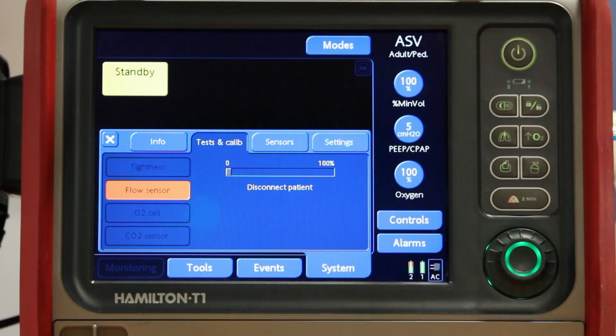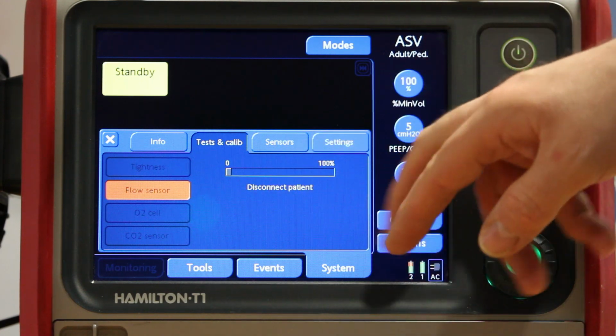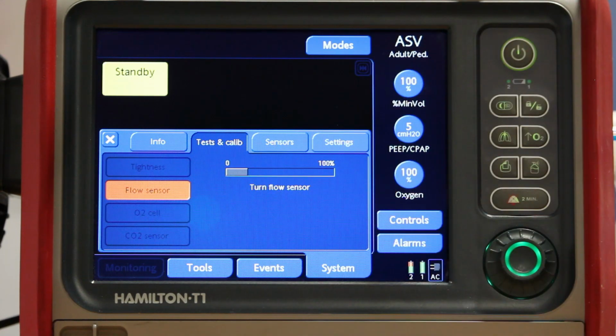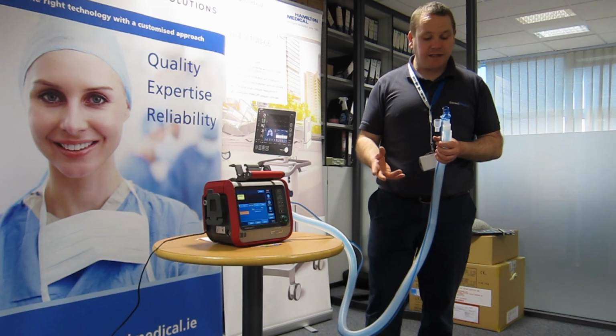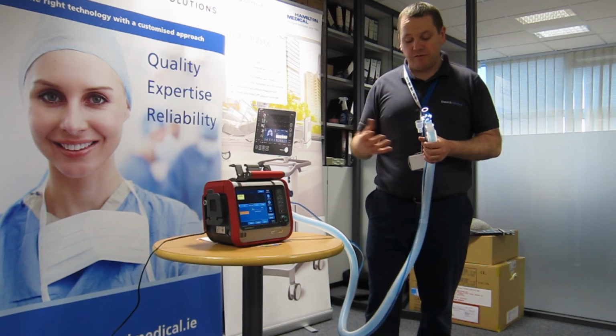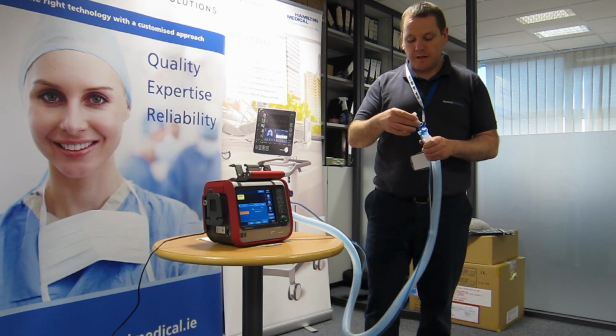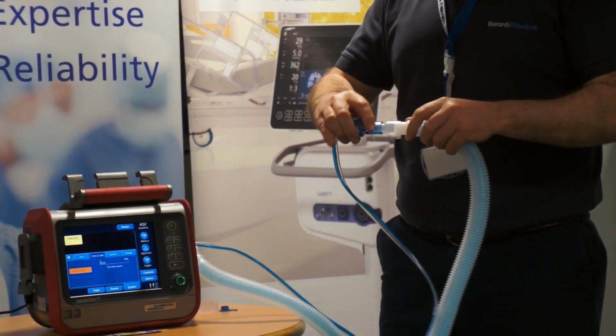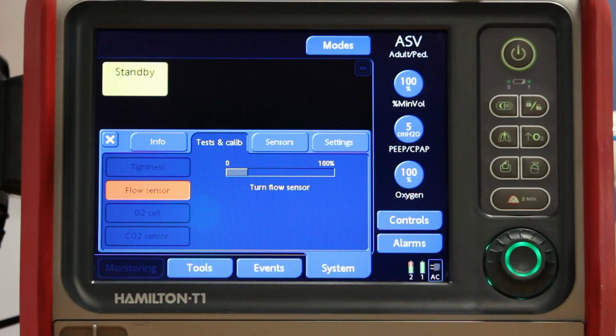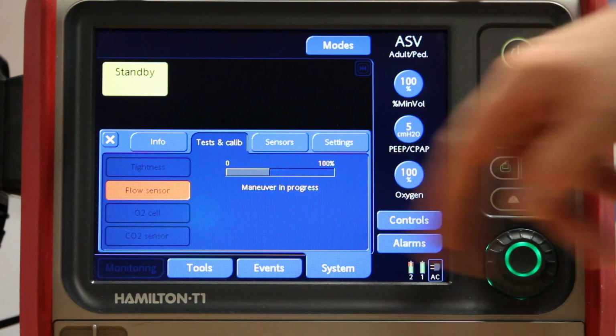So I hit flow sensor, it tells me to disconnect the patient. The first thing it prompts me to do is to turn the flow sensor. I only have 15 seconds from each prompt, or else it will fail and make me start again. So if I don't do this manoeuvre within 15 seconds, it will fail. So I turn it around, then it says manoeuvre in progress.